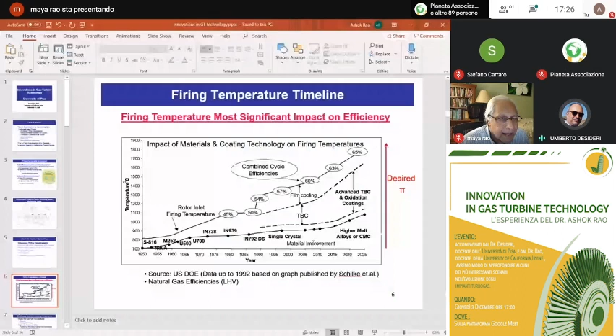So the pressure ratio also has to be increased as we increase the firing temperature, for two reasons. One, for each firing temperature there is a certain optimum pressure ratio, which tends to be higher as you go with higher firing temperature. The other is in order to limit the exhaust temperature of the turbine. The last stage blades tend to be very large because the expansion gases are near atmospheric pressure and high temperature. To avoid cooling those blades, it's better to increase the pressure ratio and limit the exhaust temperature.